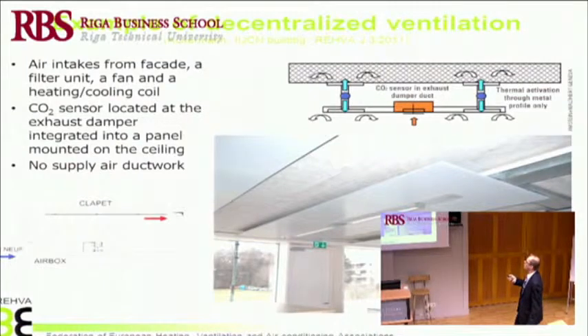But you still need some ductwork for the extract air, which is still centralized. This is one ceiling panel application used both for heating and cooling, providing radiative heating or cooling, quite commonly used in Central Europe but less in Nordic countries, because we prefer radiators below the windows for heating, and in that case we don't want to invest in such large panels - it's easier to use chilled beams, a somewhat cheaper solution typical in Nordic countries.